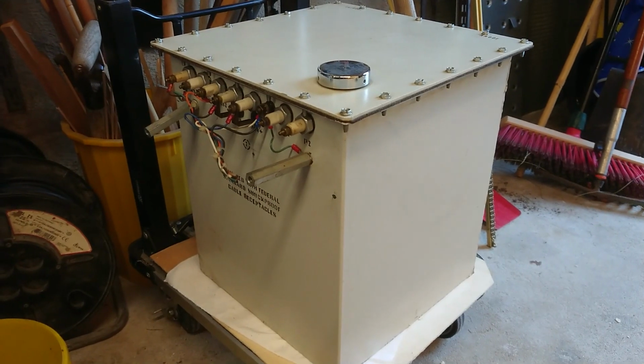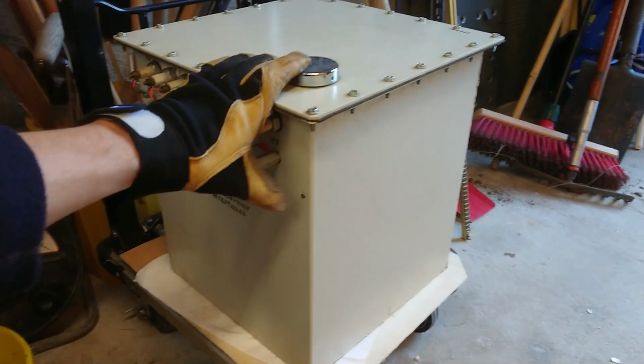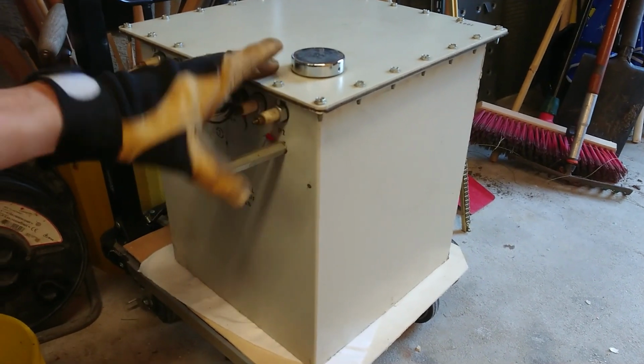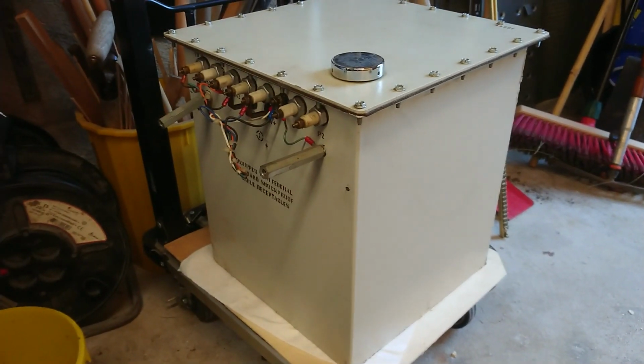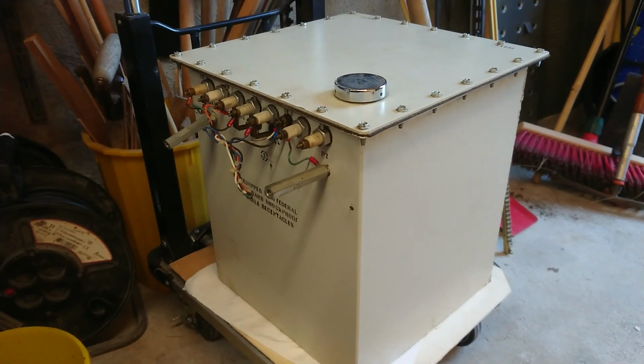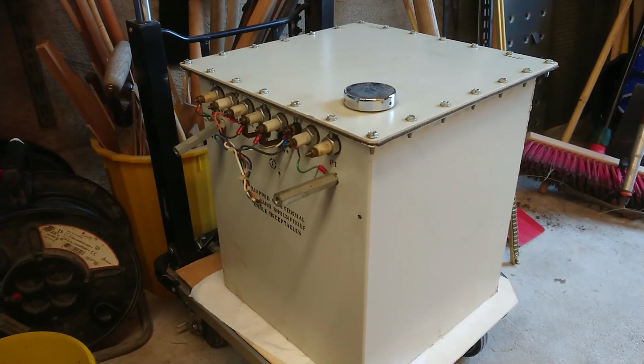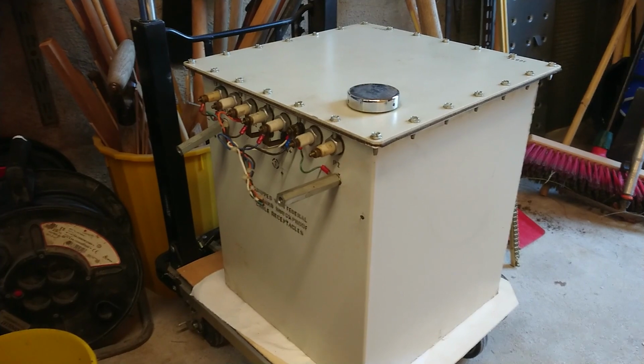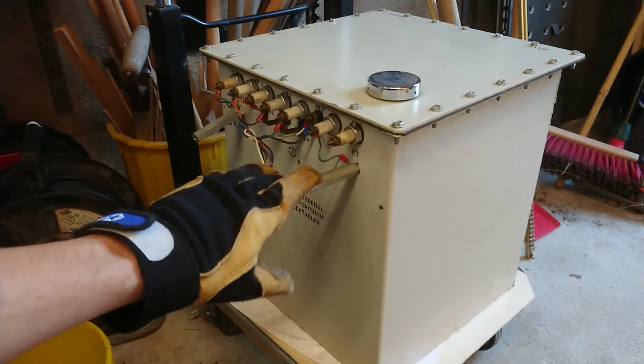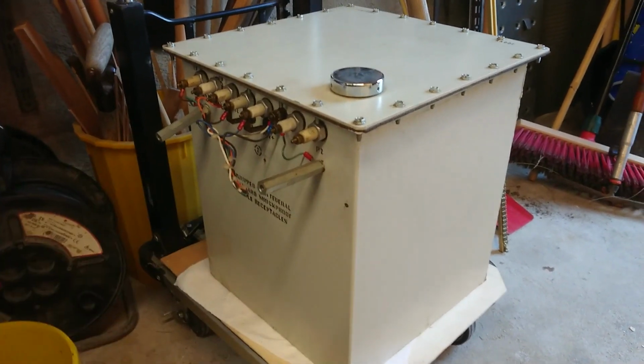The X-ray high voltage transformer is this one. As you can see by the size compared to my hand, this is a quite heavy transformer. This is a 110 kilovolt, 300 milliamp peak transformer. Here on the side it has different inputs and outputs.